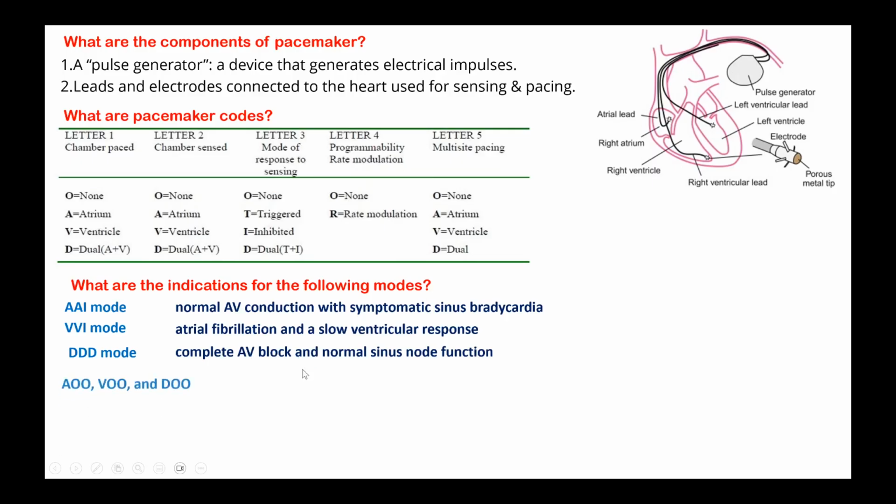Very good. And if it is AOO, VOO, or DOO, what is this? If there is no sensing, there is no response to sensing.